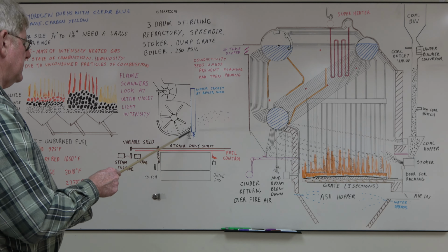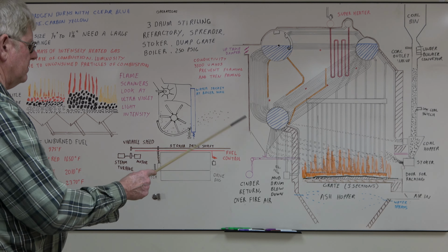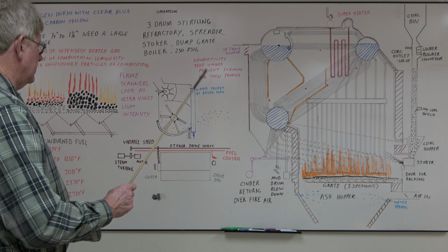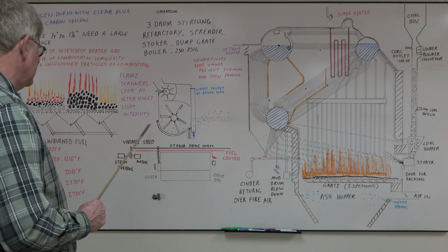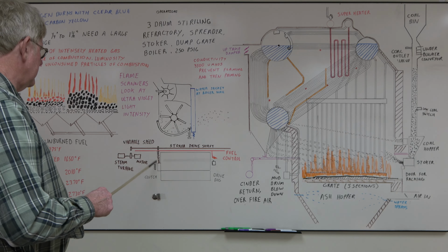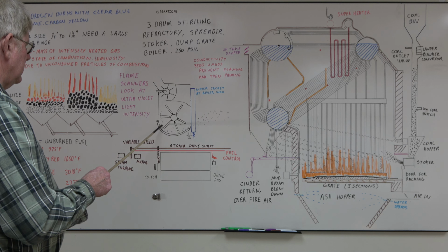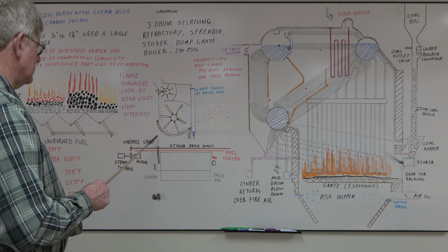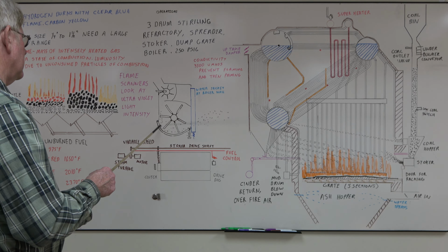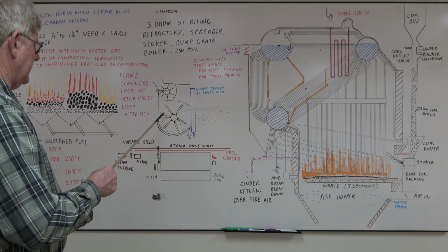This tray was adjustable. You had a bolt on it. You'd adjust this to the right arc to throw the coal out uniformly. Then you adjust the speed of your paddle wheel to control the feed rate, how well it spread it. You had a shaft run down the front of the boiler. There's 5 stokers ran off it, chain driven, with a clutch on it. So if this thing jammed, got a rock in here or a stick, it'd jam the stoker and shut the whole shaft down, so you have to pull the clutch and then get the stick or rock out of here. You may have to drop the trays and get it to work. Sometimes you could roll it backwards by hand and get it.